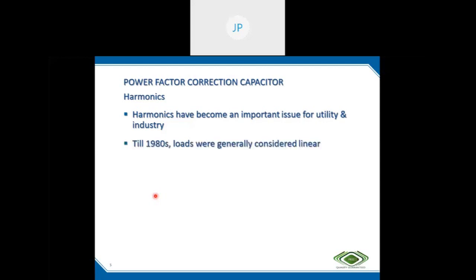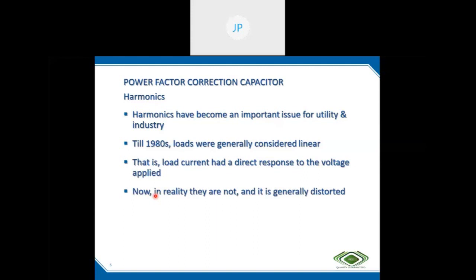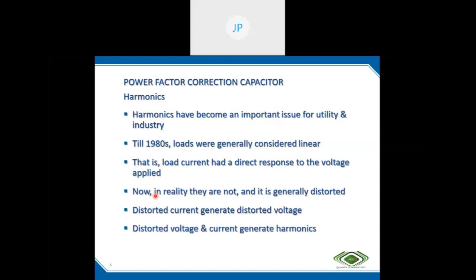Till 1980, the load was generally considered linear. Linear means the load current follows the voltage waveform. Both were sinusoidal waveforms. But actually now it is not correct. The reality is different. It is generally distorted. Distorted current generates distorted voltage and current generates harmonics.